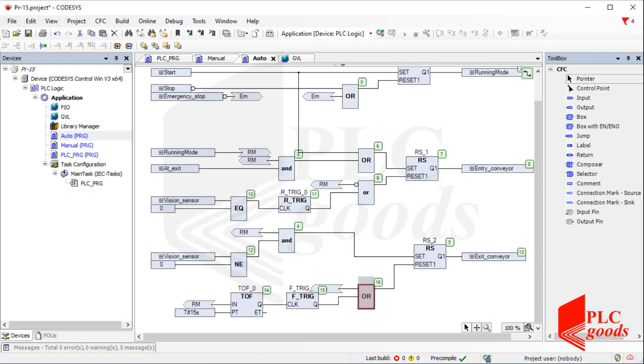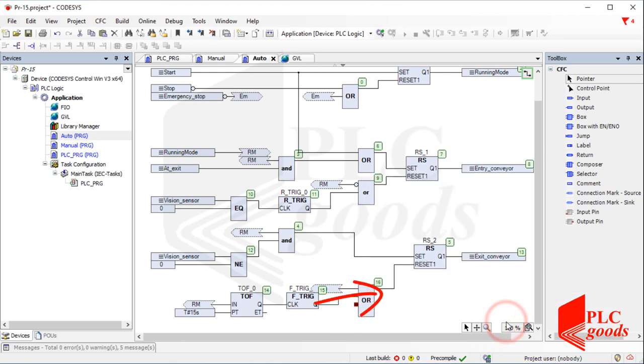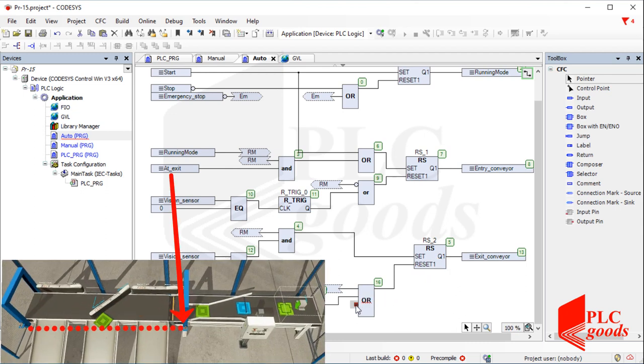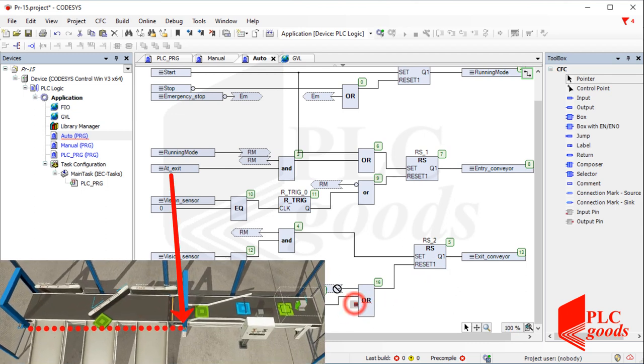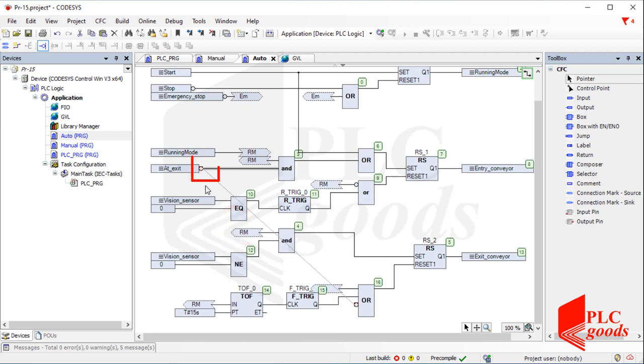Let me sort my program a little. Now let me add another pin to the last OR, because there is another condition that can stop the exit conveyor. When this sensor detects a product, it means the exit conveyor has moved a product completely and must be stopped until the next one. Note that the state of this sensor is equal to 1 in normal conditions, so I need to invert it, but not twice — please delete the second one. Note that I found this problem after recording and testing the current project.